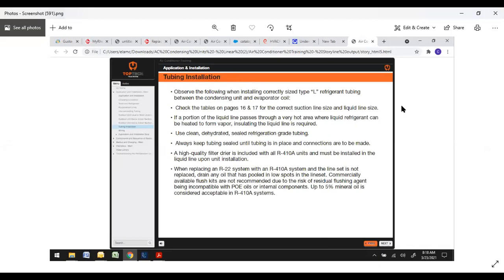Tubing installation. Observe the following when installing the correct size type L refrigerant tubing. Check on tables page 16 and 17. Like I say, we'll get that in towards the end. This is a big one. If a portion of the liquid line passes through a very hot area where liquid can be heated to form vapor, you must insulate that liquid line.